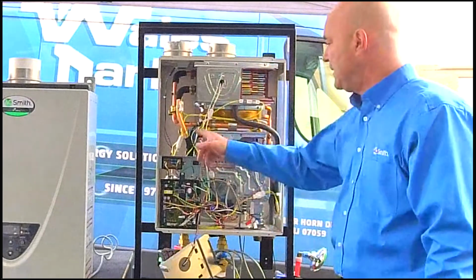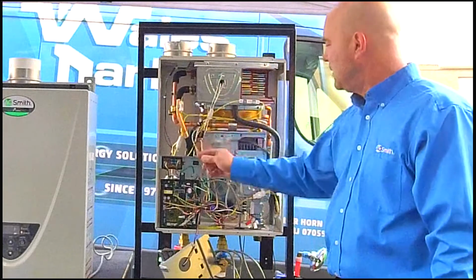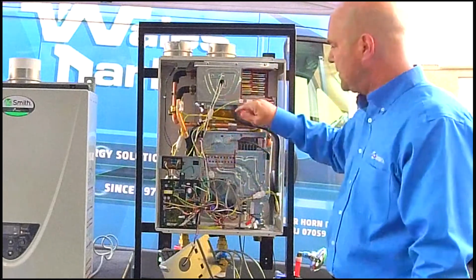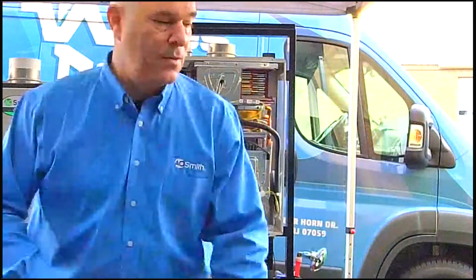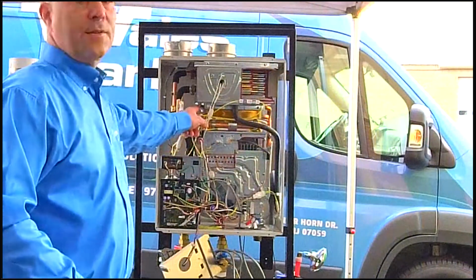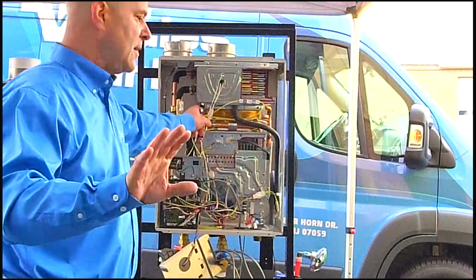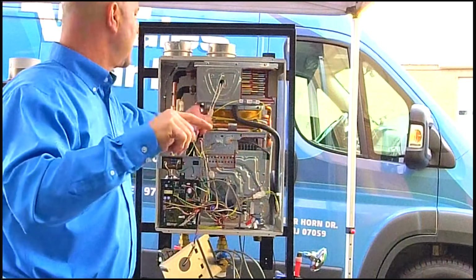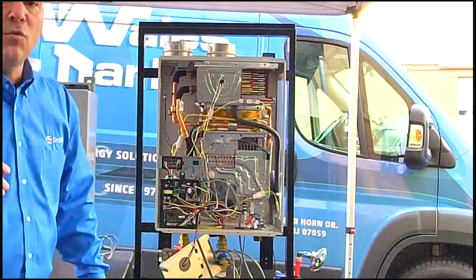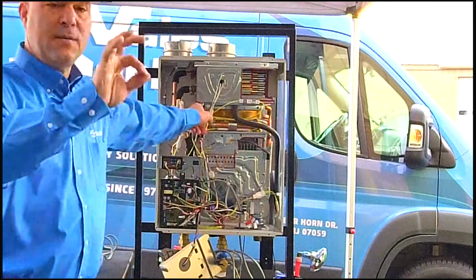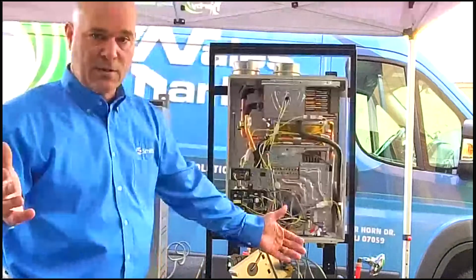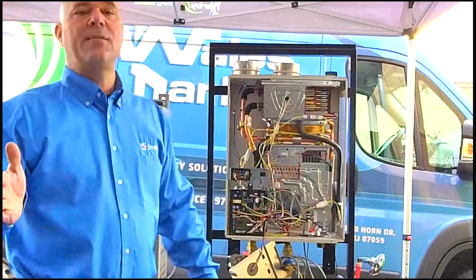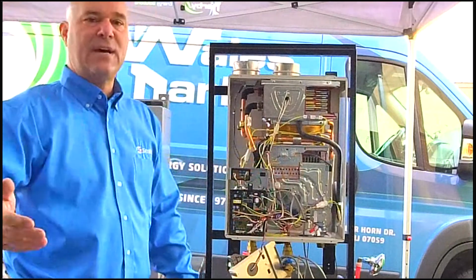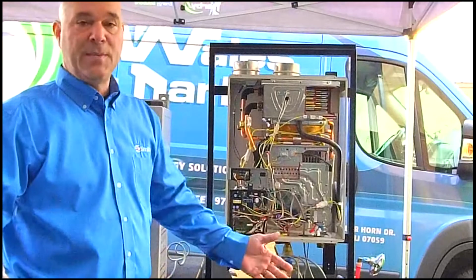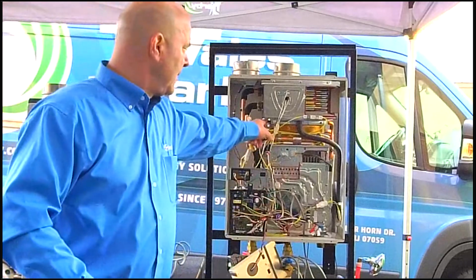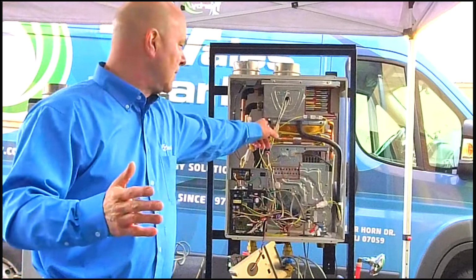Also on the safety circuit side, any blue wire that you see, this blue wire wraps all the way around the heat exchanger. That blue wire connects to a little reset Klixon. If we overheat the heat exchanger, this little red button will pop out and you'll get a service call. What that's telling us is either on the water side or on the combustion side, we're dirty and we need to be cleaned.